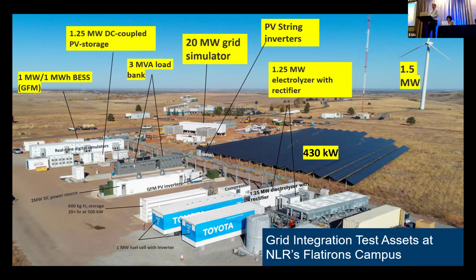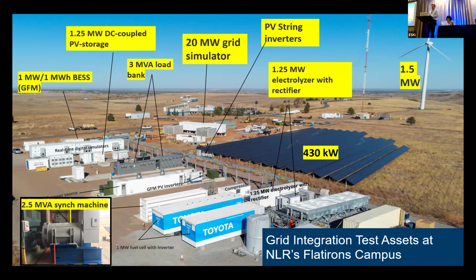We have 2 dynamometers, 2.5 megawatt and 5 megawatt. And we actually developed our first grid simulator, more or less to support the voltage ride-through testing of wind turbine systems. Over the years, we saw the value of adding these additional IBRs and the value of testing them with the grid simulator. So we've had batteries, we've got a hydrogen fuel cell and electrolyzer system. We've got the original 7 MVA grid simulator. We added the 20 MVA grid simulator. And we also have a 2.5 megawatt or MVA synchronous machine. So we use that to emulate or actually act as a synchronous condenser. And we can emulate conventional generation systems such as gas turbines and steam turbines with that.